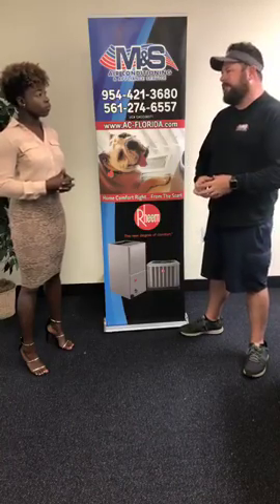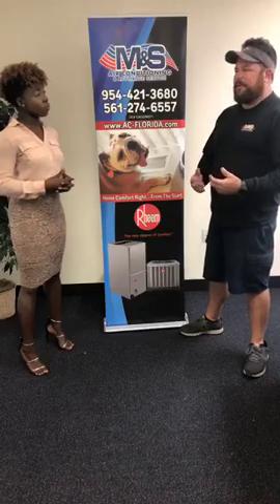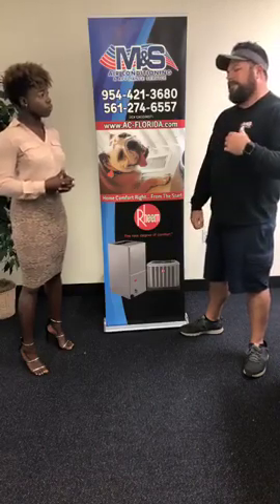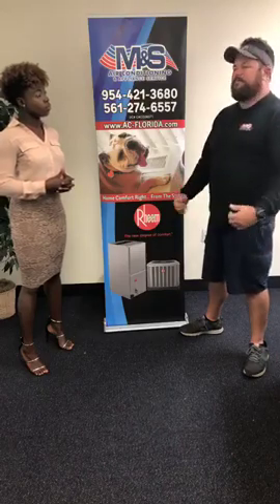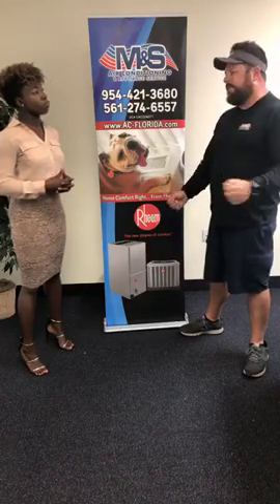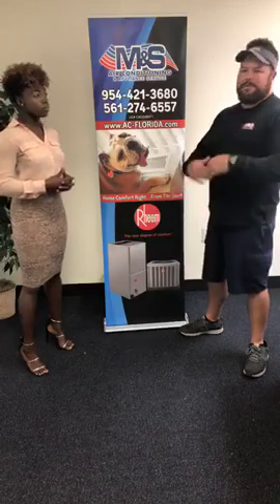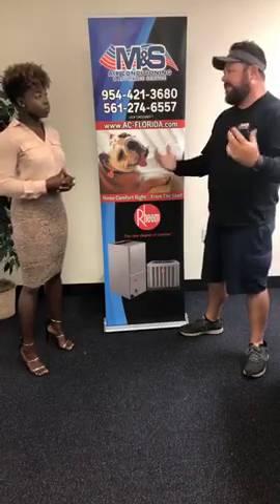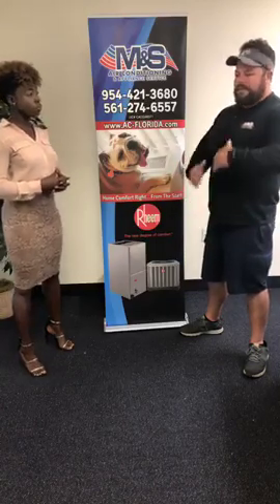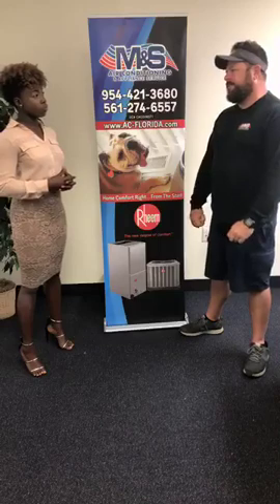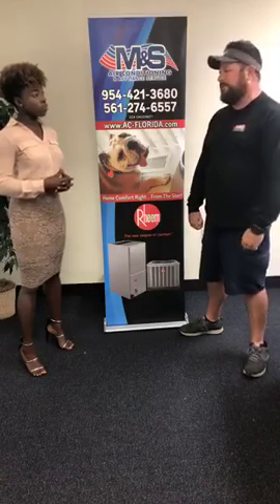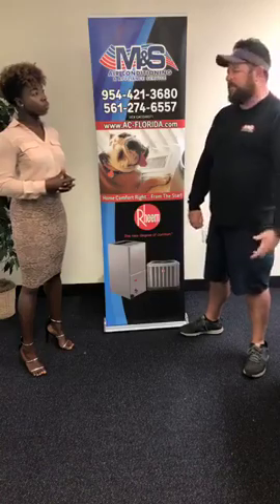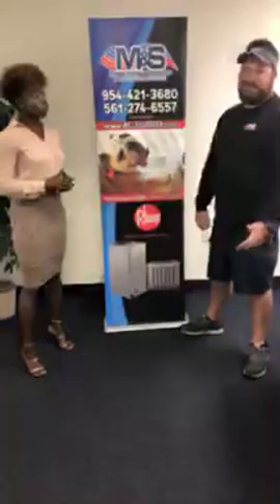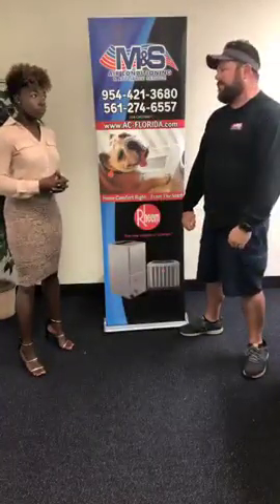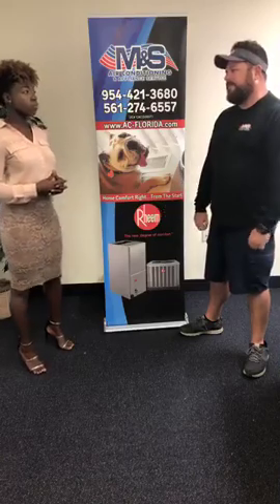The most important thing about a maintenance plan is it keeps the unit running at operation standards. Especially in South Florida, a lot of leaf blowers blow dirt into the condenser coils outside, restricting the air going into the unit, and that can make the unit malfunction prematurely. You want maintenance done at least twice a year because of those issues. Basically an air conditioner in South Florida is like running your car at 90 miles per hour in second gear, non-stop.